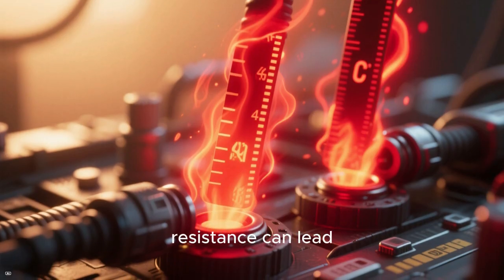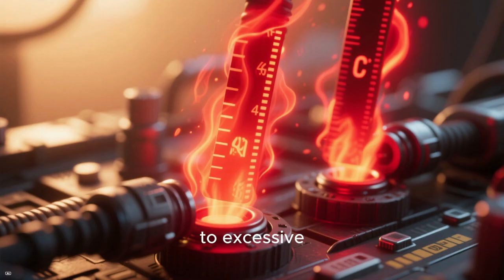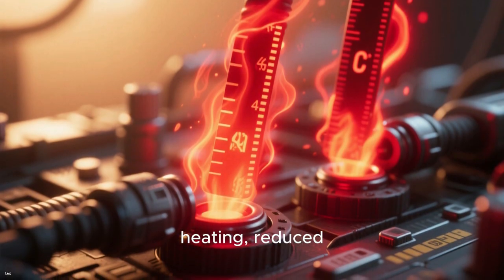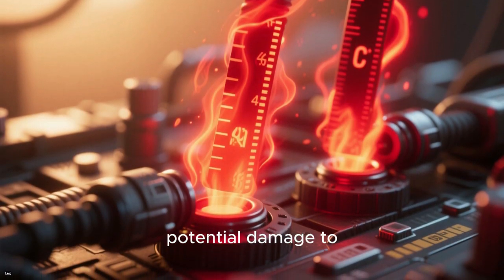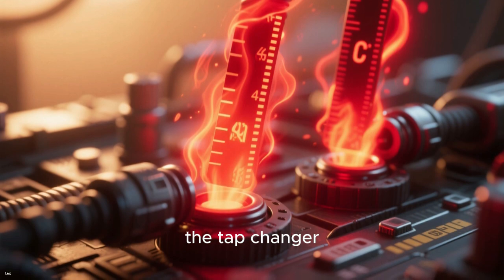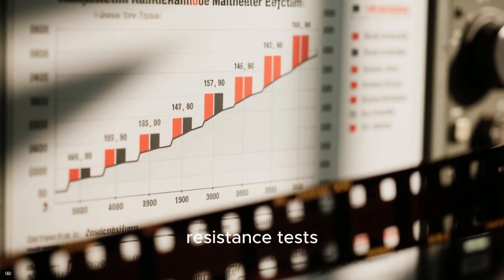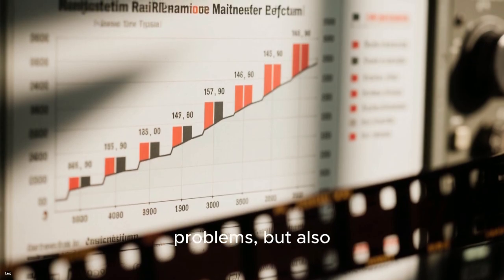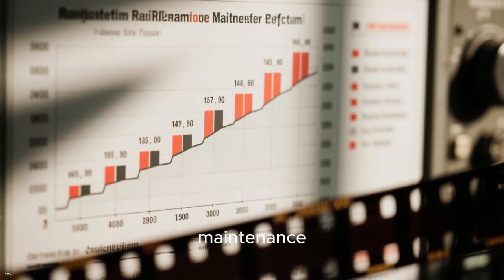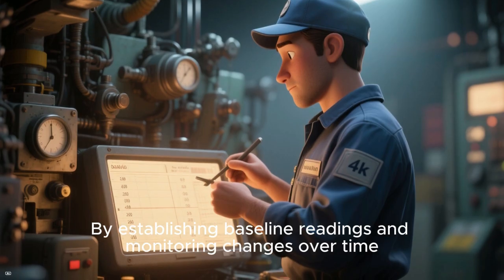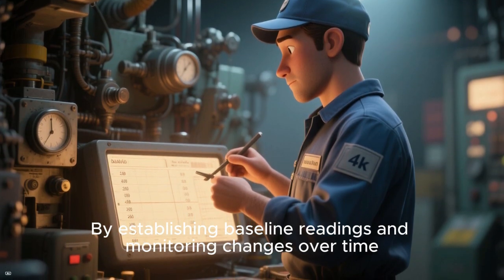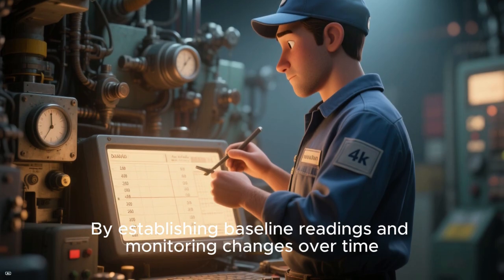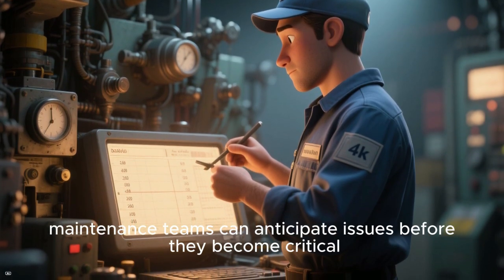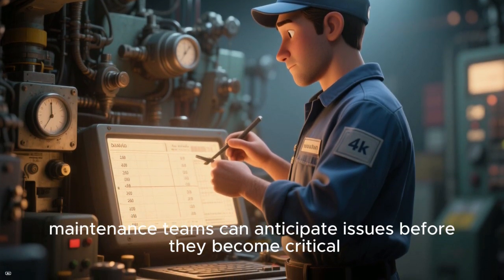High contact resistance can lead to excessive heating, reduced switching capabilities, and potential damage to the tap changer. Performing regular resistance tests not only helps in identifying problems, but also provides valuable data for predictive maintenance strategies. By establishing baseline readings and monitoring changes over time, maintenance teams can anticipate issues before they become critical.